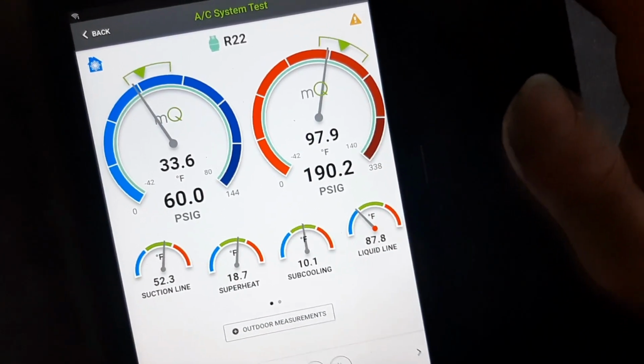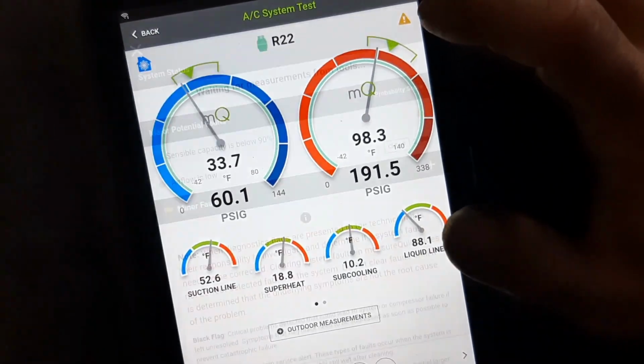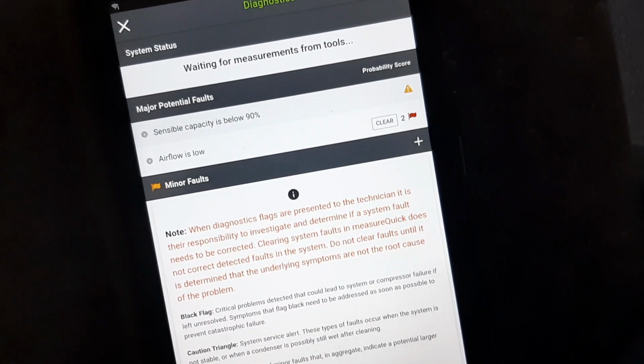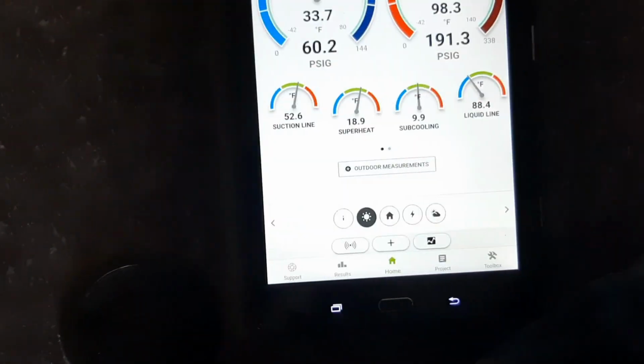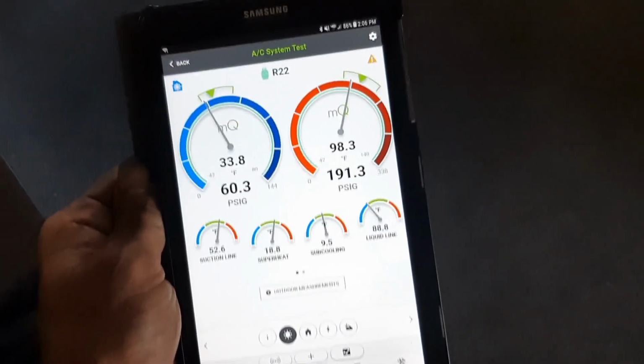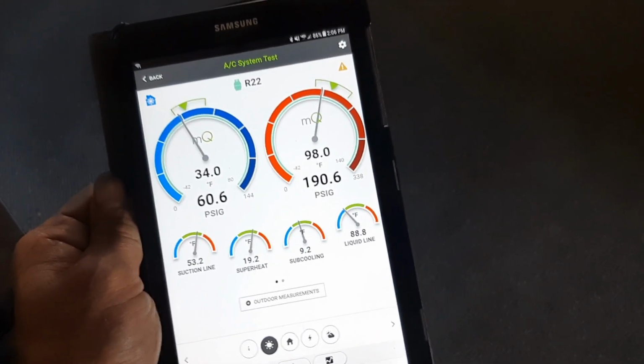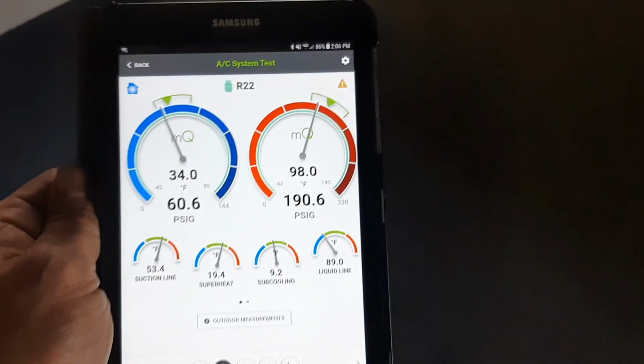So this one evened out. We're still, might be a little low on charge, but airflow and sensible capacity is what Measure Quick's saying. But again, it's 35 or so years old, so let's switch over to the other one and see what it looks like. It looks reasonable. Expansion valve's at least maintaining some superheat, so one more to go. We'll see how bad that one is. We've already satisfied up here. I went ahead and kicked my temperature back up. We'll do the same on the others. We'll just leave them set at 73 or so. Go from there.